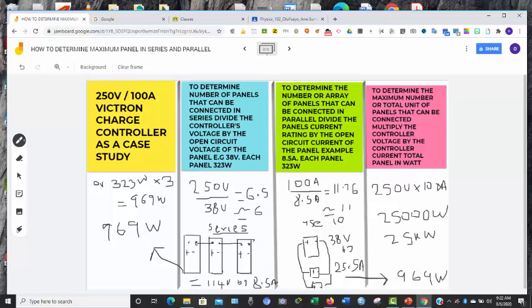To know the maximum number of panels that can be connected, we need to divide the voltage of the charge controller by the output voltage, or open circuit voltage, of one of the panels. In this case, I've divided it and I have 6.5. That is 250 volts divided by 38 volts. This 38 volts is the open circuit voltage of one of the panels, and I'm able to get 6.5 panels. We have to round this up or down, because you cannot have half a panel. So instead of using 6.5 panels, we will use six panels.